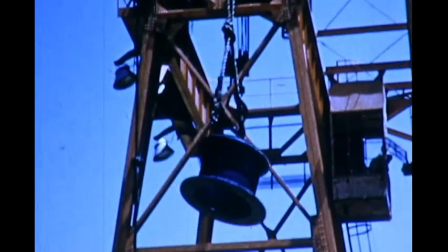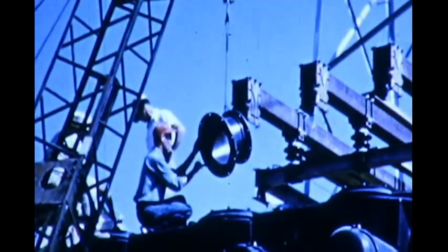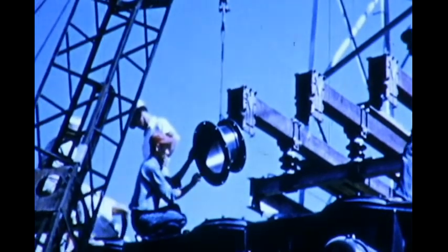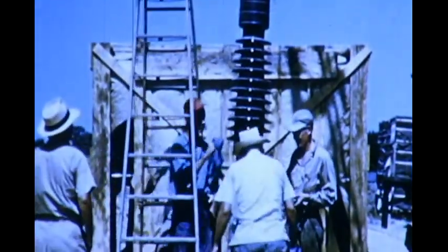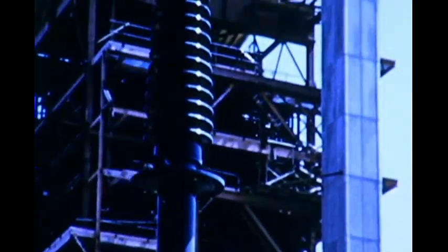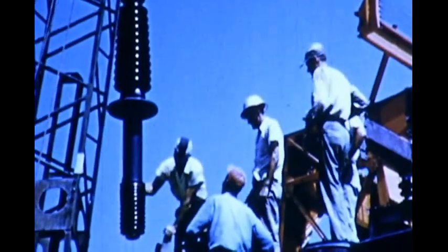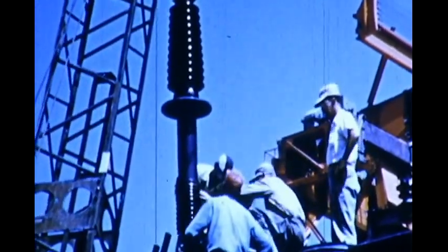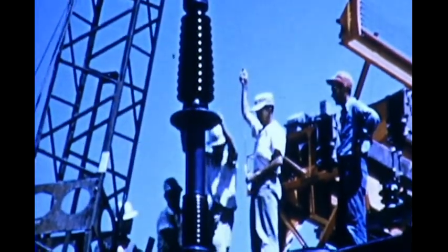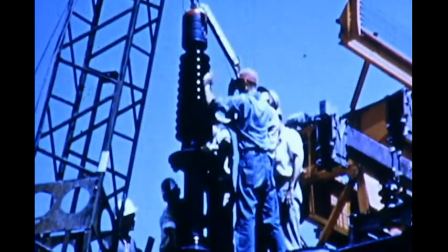Each bushing is mounted to the tank by one of these adapters that is bolted in place with the same nitrile gasket used for shipment. The bushings themselves, after removal from the shipping crates, are cleaned and then carefully raised to the transformer. Special lifting eyes on the bushings are provided for the lifting cables. Once the bushing is ready to be set down, a small wire is used to draw the cable through the bushing tube. And the bushing is then lowered slowly into the adapter.